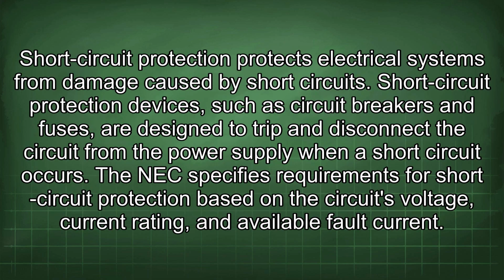Short circuit protection protects electrical systems from damage caused by short circuits. Short circuit protection devices, such as circuit breakers and fuses, are designed to trip and disconnect the circuit from the power supply when a short circuit occurs. The NEC specifies requirements for short circuit protection based on the circuit's voltage, current rating, and available fault current.